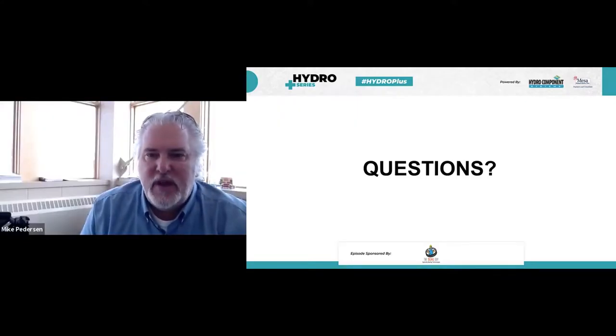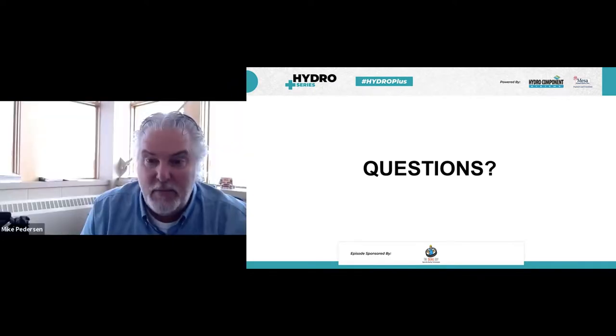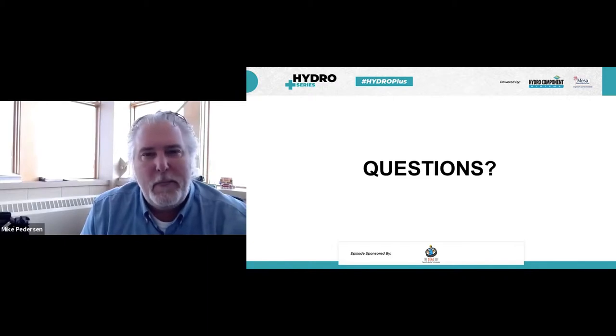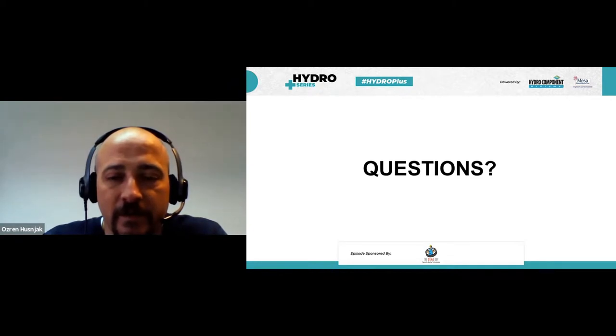Another question: stiffening a unit in resonance is based on the mode shape of the natural frequency. This would look like a cantilever type mode. Any reason why they stiffened the bottom, which is most likely close to the node? Yes, we found that out at the beginning. When we first came there, it was the easiest thing to do. Some good results could probably be had by stiffening the top of the generator too, but no construction could be made that easily. When we found out that there was a problem below the spiral, we focused there and saw where the concrete injection would get us.